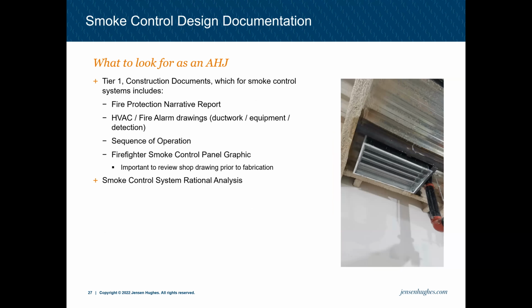Near the end of construction documents, that's when you submit design documents to the building inspector for a permit. AHJs tend to look for your tier 1 documents, which are generally created by your MEP engineer, MEP, FAFP, depending on how it's rolled out. But that should include a fire protection narrative report, obviously HVAC and fire alarm drawings, which will include a sequence of operations. Typically, there's some type of reference to a smoke control panel in these documents. Whether they are explicitly in there or not is somewhat questionable.